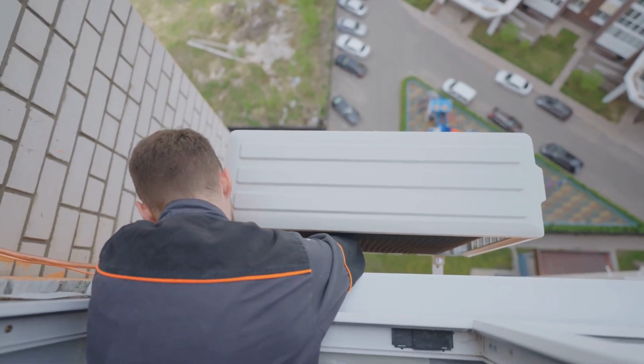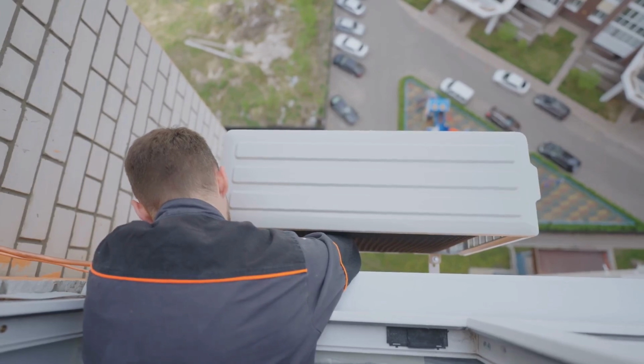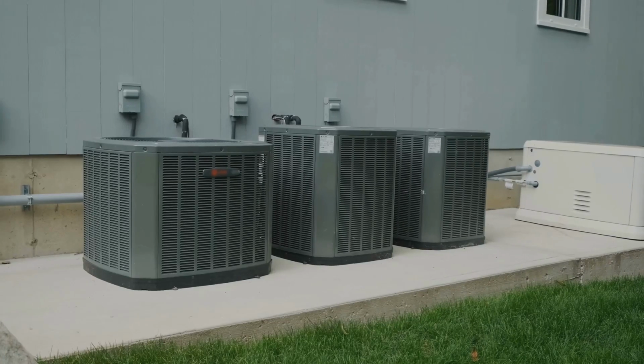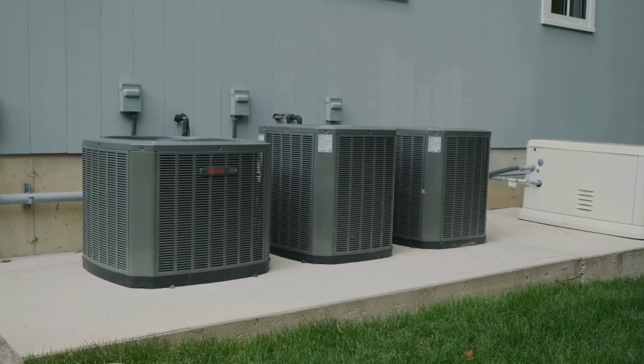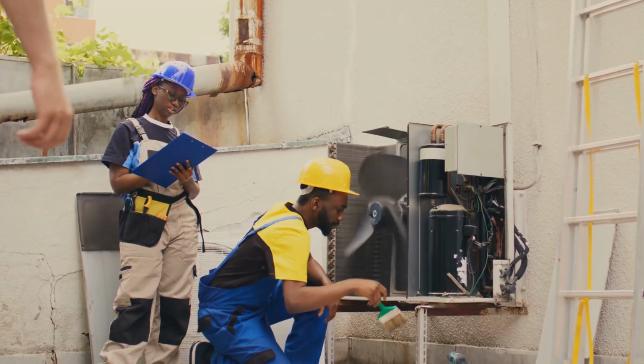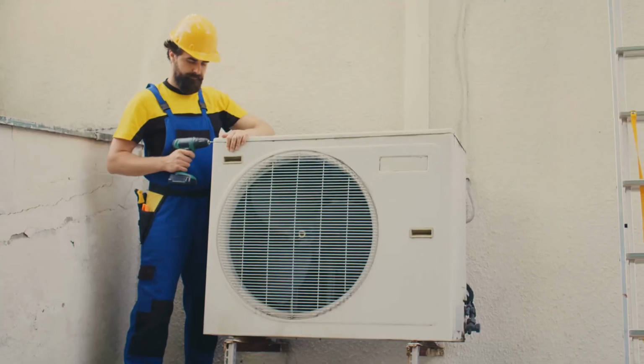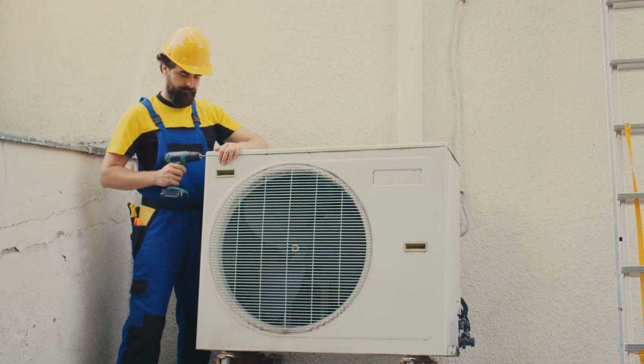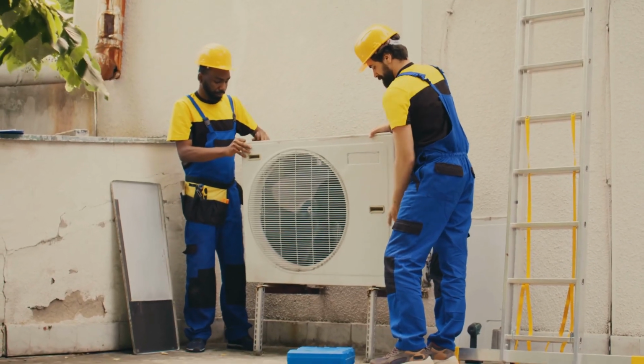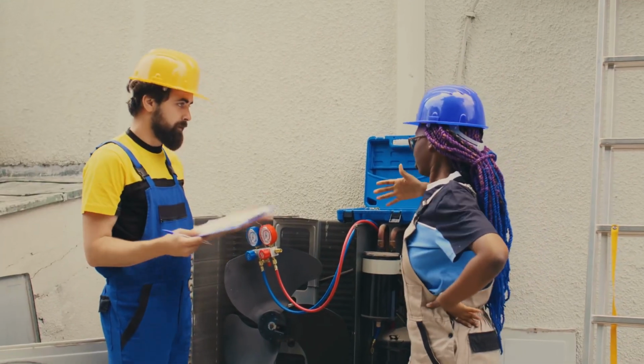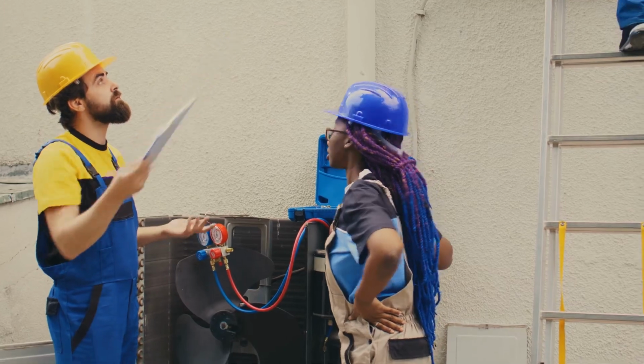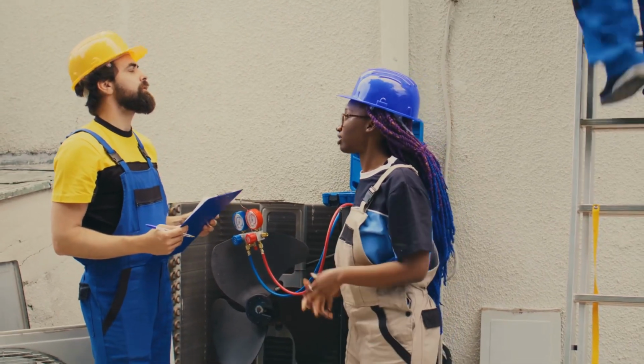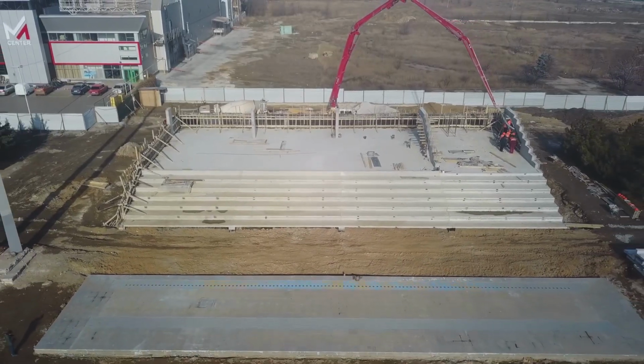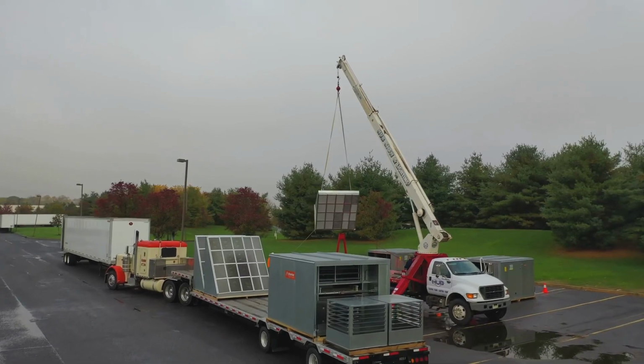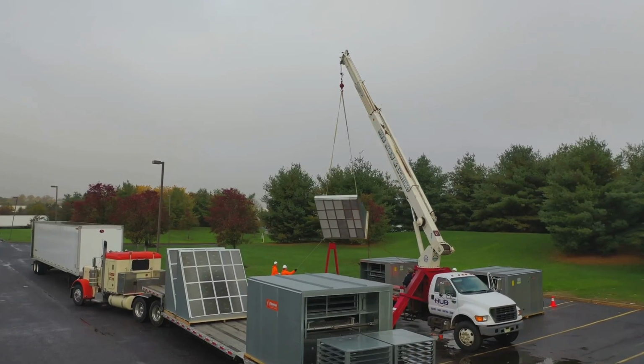Section 7. Outdoor Unit Installation Step-by-Step Guide. Installing the outdoor unit typically involves placing it on a level pad, connecting it to the indoor unit with refrigerant lines, and making the necessary electrical connections. Step 1. Prepare the pad. Choose a location for the outdoor unit that is level, well-drained, and provides adequate clearance. If needed, you can construct a concrete pad or use prefabricated pads designed specifically for AC units.